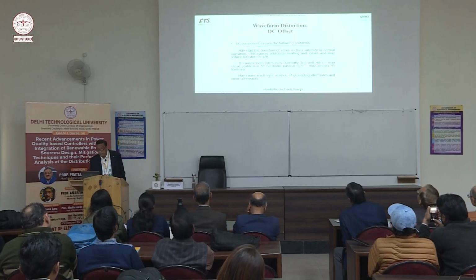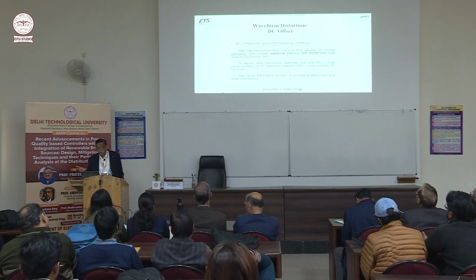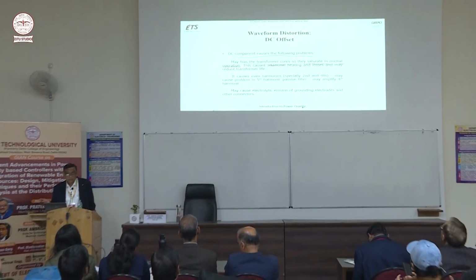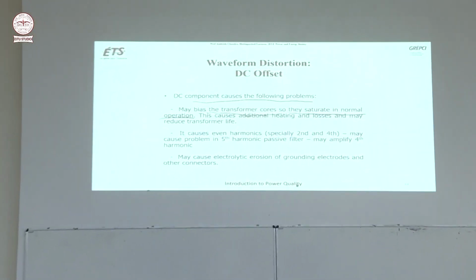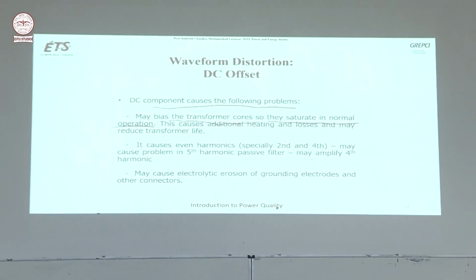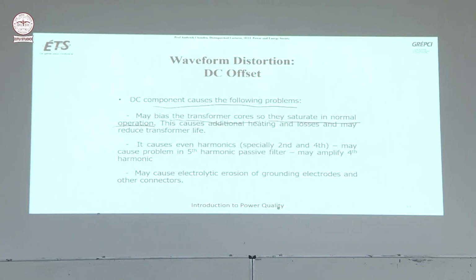DC component causes the following problems. It may bias the transformer core so it saturates in normal operation. So basically you have to derate the transformer. If the core is saturated, you cannot run the transformer at 100% load. You may have to derate it, otherwise it may heat up because of the additional losses and may reduce the transformer life.